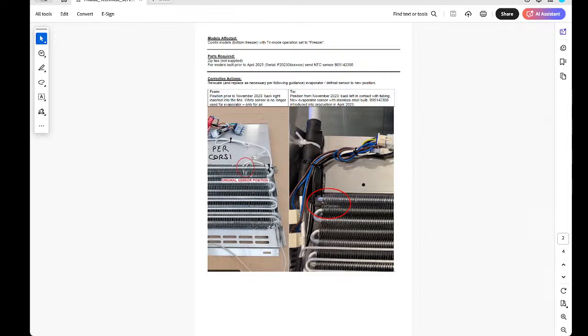That way we have less of an issue where the unit does not go through a proper defrost and then have issues with airflow. And when we have a lack of airflow, then the unit's not going to cool properly. And the first thing it's going to do is the machine's not going to make ice. And that's going to be the customer's complaint. They're going to call us, let us know that they're not making any ice and that the temperatures have been a little wonky. Sometimes they'll hit 45, sometimes they'll hit 38, but it's never a consistent temperature. When you run into those things, give us a call, check out that technical service bulletin, log on to the Fulgor Milano reserve site. The technical service bulletin is on there as well. That way we can all take care of these customers.